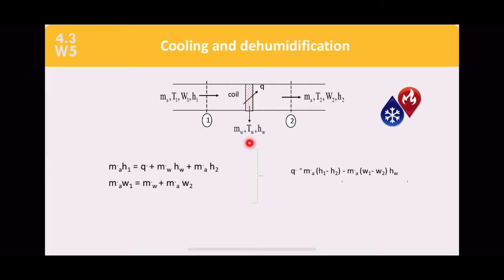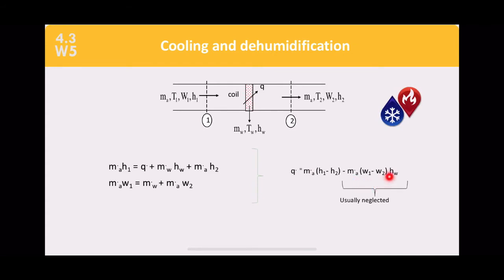The main equation is: Q = m_a·(h1 - h2) - m_a·(ω1 - ω2)·h_w. The cooling load involves two components: the enthalpy difference and the moisture removed via condensate. Sometimes the condensate term is neglected when only air is used in the load calculation. For latent cooling, the moisture term must be included.